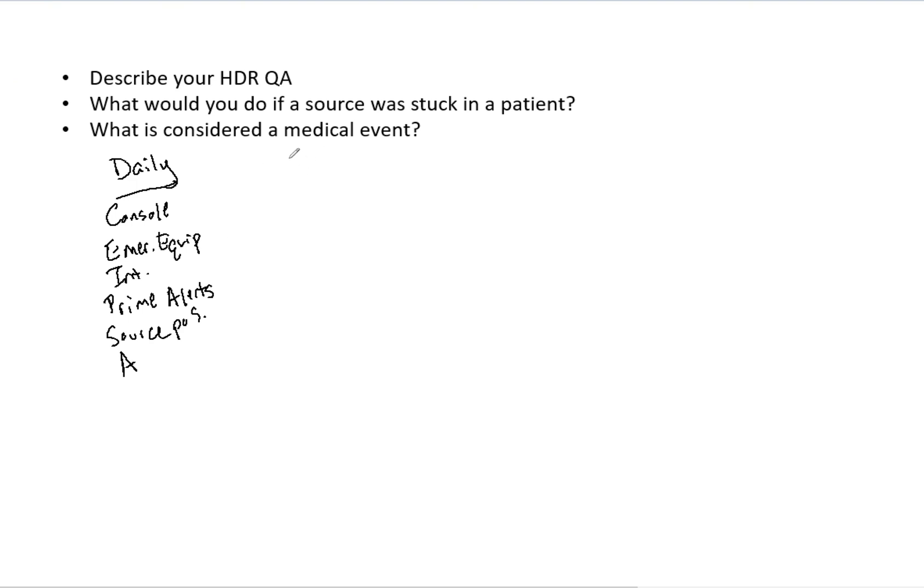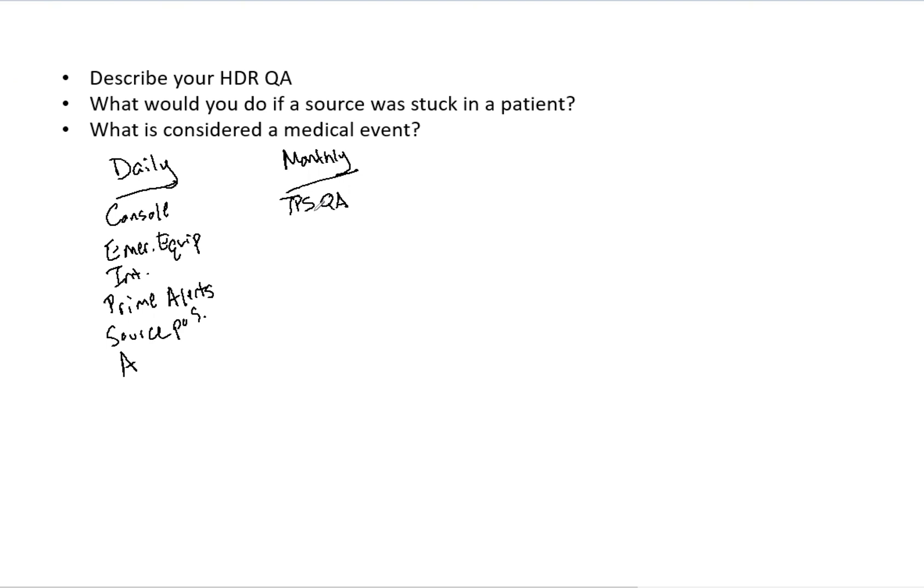And so next we've got our monthly or quarterly QA here. So first thing you should ideally do TPS QA on your HDR unit as well in your software. This includes doing importing and verifying of CT numbers and the geometric accuracy of your TPS. So that's monthly. And then if we want to talk about quarterly, let's talk about the source exchange that's done. And that's the exchange activity.